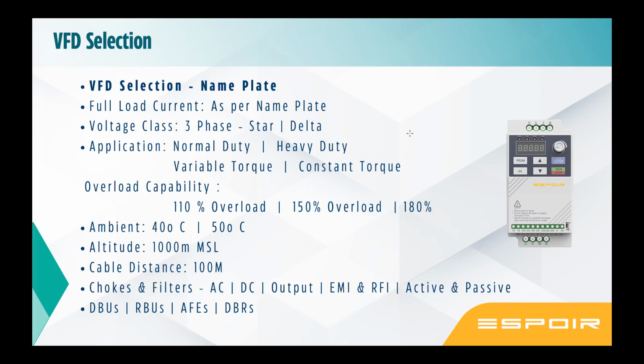And in an industrial environment, where there is an issue of ventilation, the internal temperature is higher, so safely consider the ambient to be more than 45 degrees Celsius. You need a drive which will withstand 50 degrees. If for 11 kilowatt, 22 amps is the rated current, it means that it can deliver 22 amps at 40 degrees Celsius. That is as per the design. If your environment is going to be 45 degrees, you need to derate the drive.